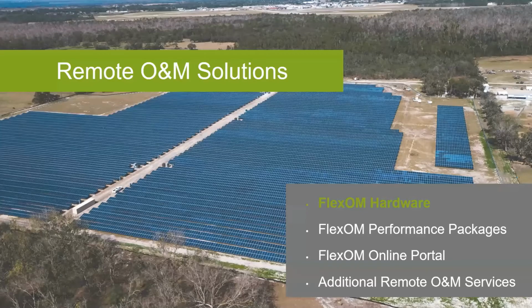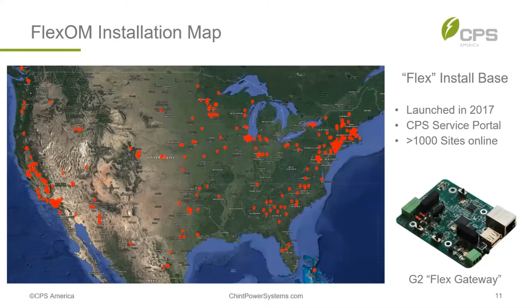Let's look at the details of the FlexOM hardware, starting with some history. The CPS Flex Gateway, the forerunner to the FlexOM, was a communications and controls solution for CPS inverters introduced in 2017. It was a Modbus master data logger and communications device that managed traffic for three parallel outbound communication options: a local pass-through Modbus RS-485 connection to a third-party data logger solution, an Ethernet-based connection for a CPS web-based service portal, and a programmable Ethernet-based connection to a local location chosen by the customer.